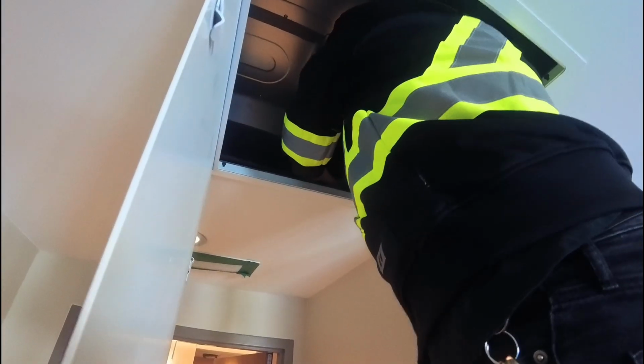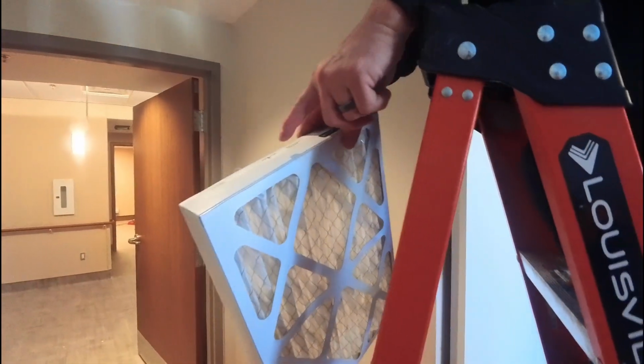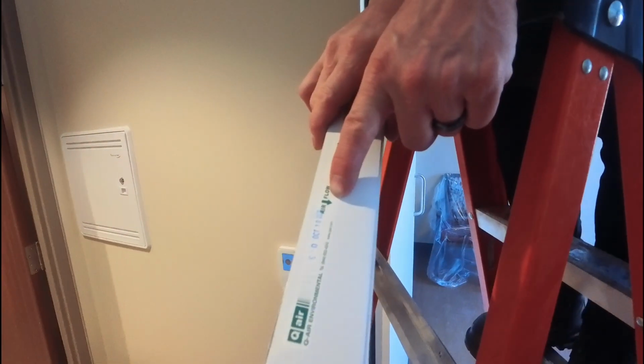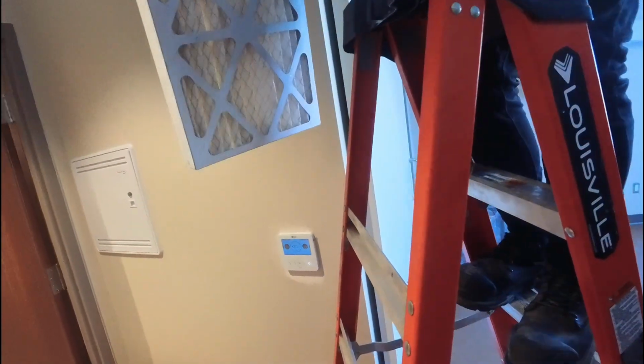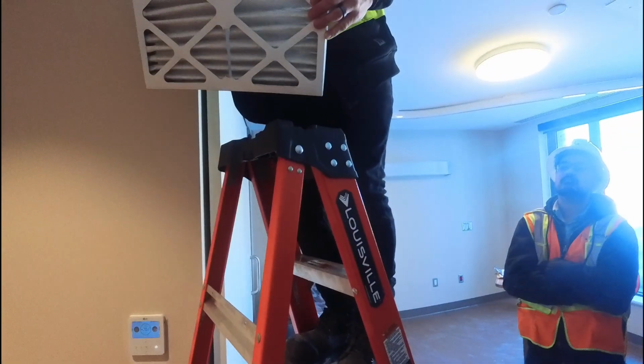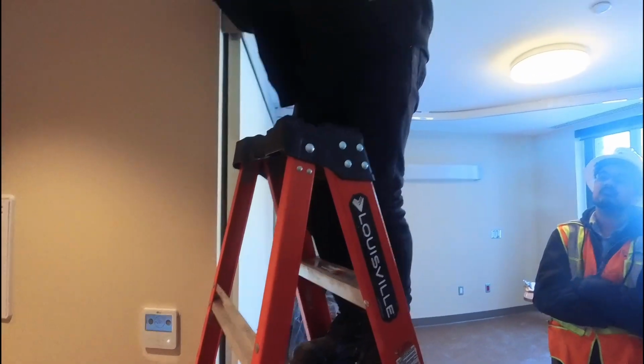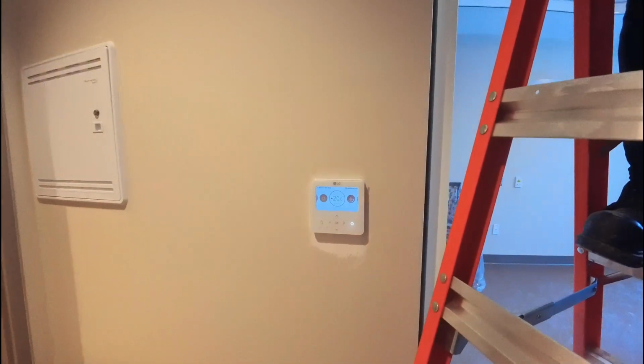There we go. And they just slide out. There are two filters in there, and the filter will slide. And once again, when you're changing those filters every 3 months or so, or 6 months, I'm not sure what it's called for, watch out for the arrows on the ends of the filters showing airflow direction. And the airflow always goes towards the supply diffuser, which is at the window, like we talked about before, from the return end of the unit to the supply end of the unit.